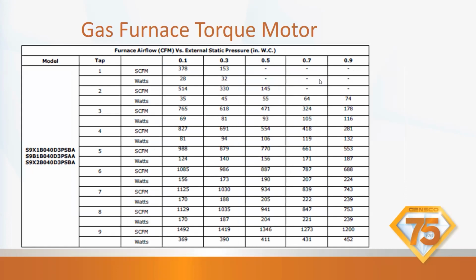S9X1 gas furnace. We're going to take our external static pressure and look at the CFMs, and determine what CFMs we need at what speed tap. Okay, if there are little dashes there, that means you're not going to get that pressure at that speed tap. You're just not going to get anything out of it, basically. This is a torque motor. On all the torque motor furnaces, if you'll notice in the books, they do not give you a setting for airflow. They tell you to check the total static pressure, and depending on the total static pressure, this is where you're going to set it to get the volume of air you need. Okay.